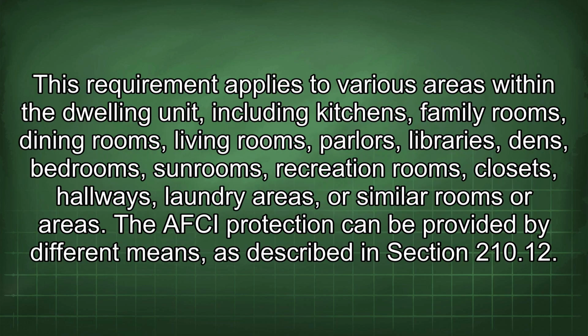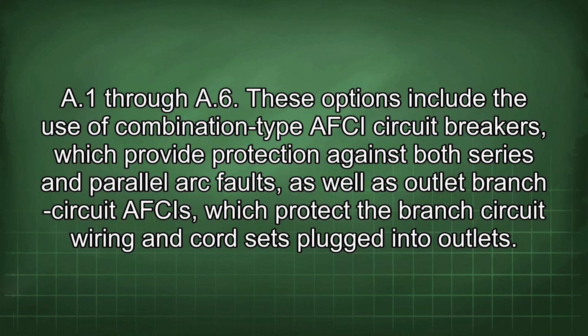This requirement applies to various areas within the dwelling unit, including kitchens, family rooms, dining rooms, living rooms, parlors, libraries, dens, bedrooms, sunrooms, recreation rooms, closets, hallways, laundry areas, or similar rooms or areas. The AFCI protection can be provided by different means as described in Section 210.12, A1 through A6. These options include the use of combination type AFCI circuit breakers, which provide protection against both series and parallel arc faults, as well as outlet branch circuit AFCIs, which protect the branch circuit wiring and cord sets plugged into outlets.